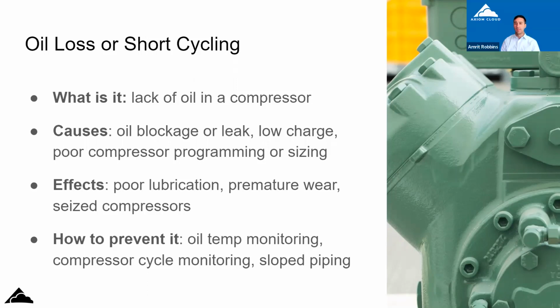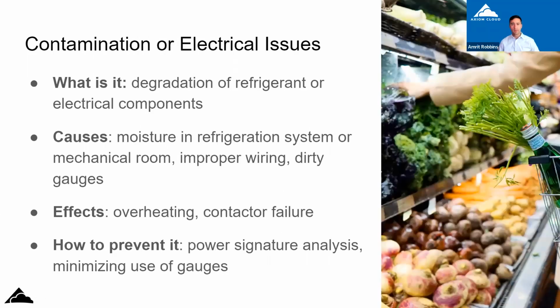And the rule of thumb that I've heard is that you've got to have compressors running for at least like 8 minutes. Does that match what you've heard? It's all different with different manufacturers. You want them at least 2 or 3 minutes for sure, but depending on the manufacturer, it could be 6 times an hour, 12 times an hour, or 20 times an hour starts. But you need to look up the compressor manufacturer specs. Yeah, makes sense. All right, let's keep going, Turner.